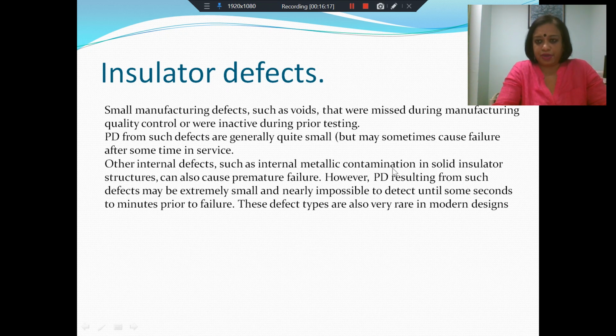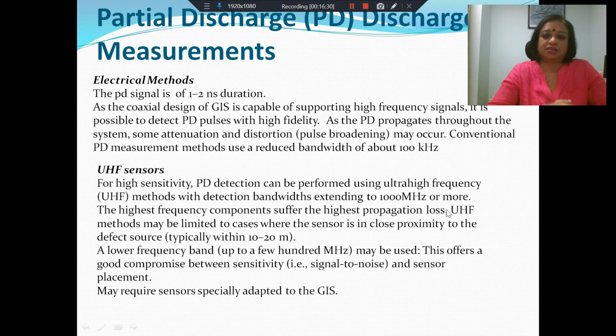Especially when you have PD inside insulators, there will be considerable attenuation of the acoustic signal before it arrives at the enclosure where you can put up the acoustic sensors. So let us therefore discuss a little more formally the various partial discharge measurement techniques that are used in gas insulated substations. The first is, of course, the electrical method.